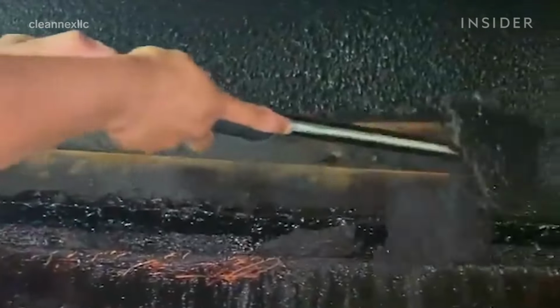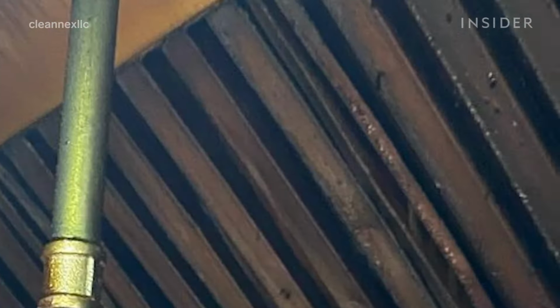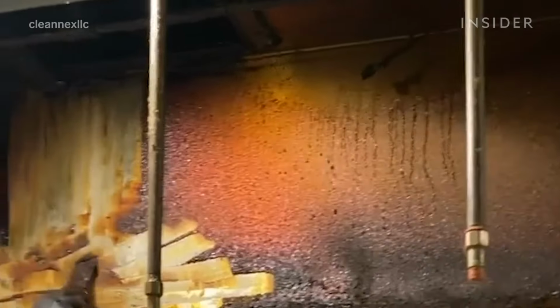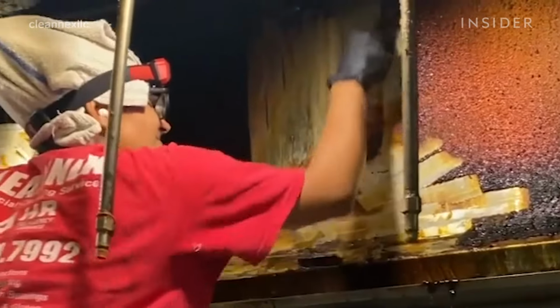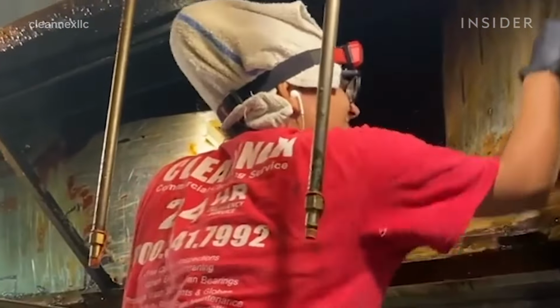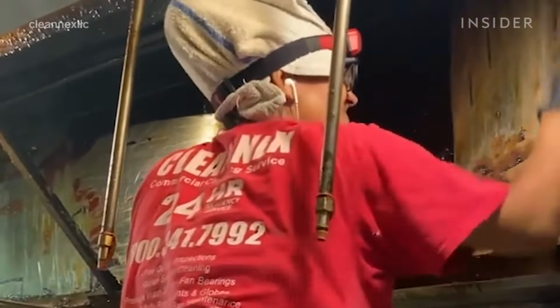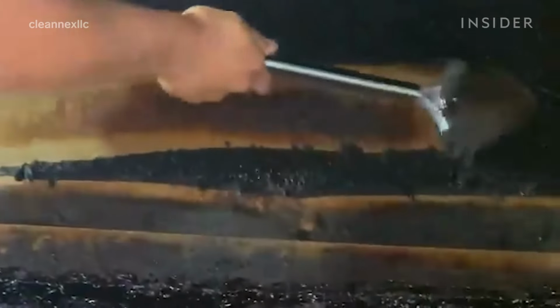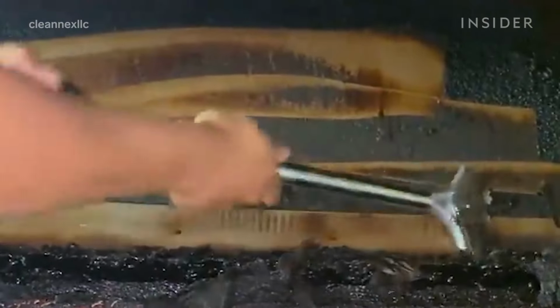The next step would be the hood and the filters. See, the filters are your first line of defense. What the filters are doing is holding back heat and they're holding back most of that grease. When the filters no longer can hold the grease, and once that grease starts getting heat and melting, you have the potential of that grease dropping into your food, and at that point, it's a health issue. I've seen restaurants been shut down by the health department for not cleaning their hood. I've seen restaurants been shut down by the fire marshal for not maintaining their hoods.